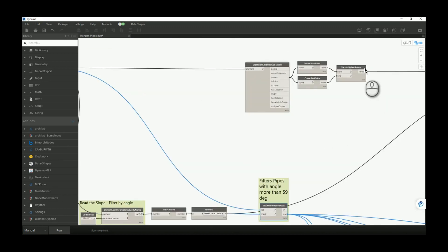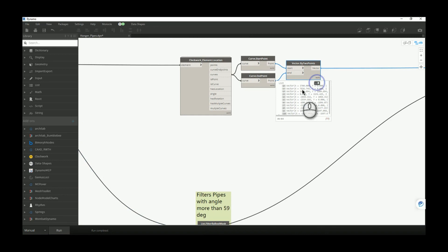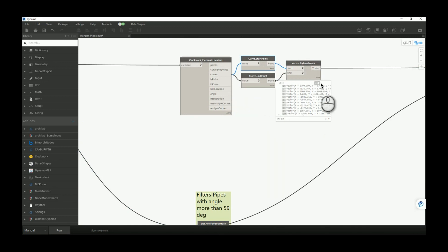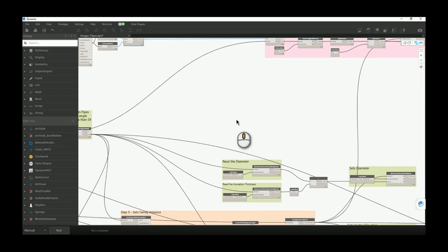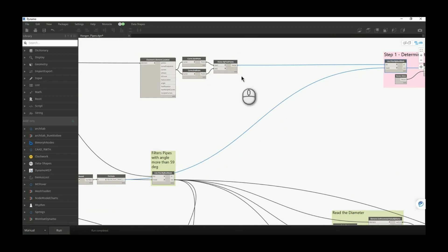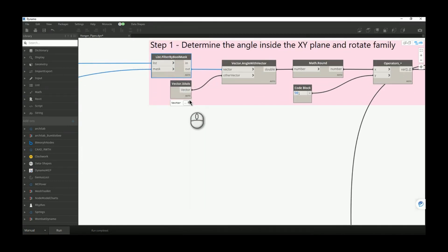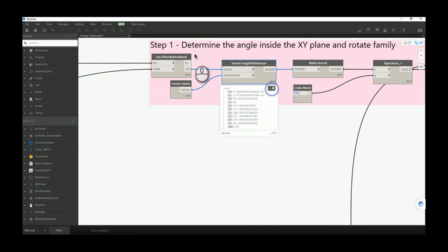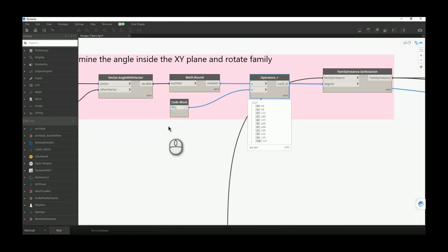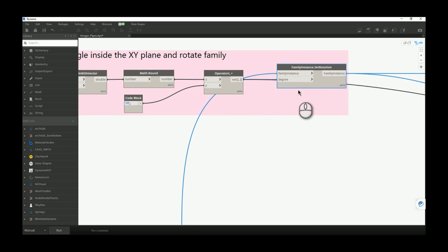I will pass all elements in the project and create a vector by detecting the start point and end point of each pipe, then creating that vector from two points. I pass this vector to this group of nodes — I have vectors for all pipes. For pipes with slope greater than 59 degrees I exclude those pipes, which is why I have this filter. I then compare my vector with the X-axis vector — the output from this comparison is an angle. I round that angle and initially rotate all hangers by 90 degrees, then I rotate all pipe hangers.